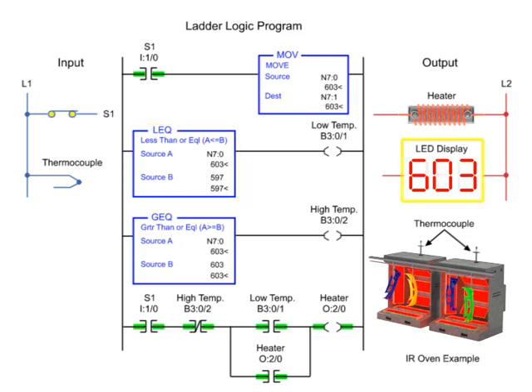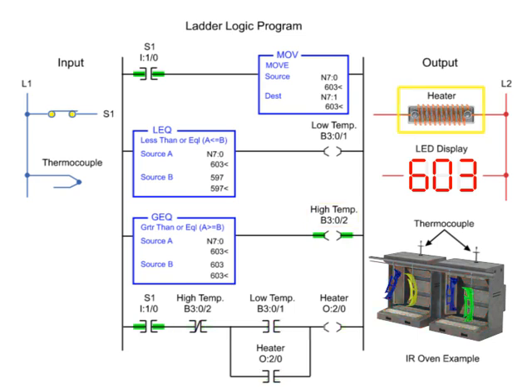Reaching 603 degrees or more, the high temp output is enabled since source A is equal to source B of the greater-than-or-equal-to instruction. When the high temp output is true, the heater turns off and remains off until the temperature reaches 597 degrees or lower.